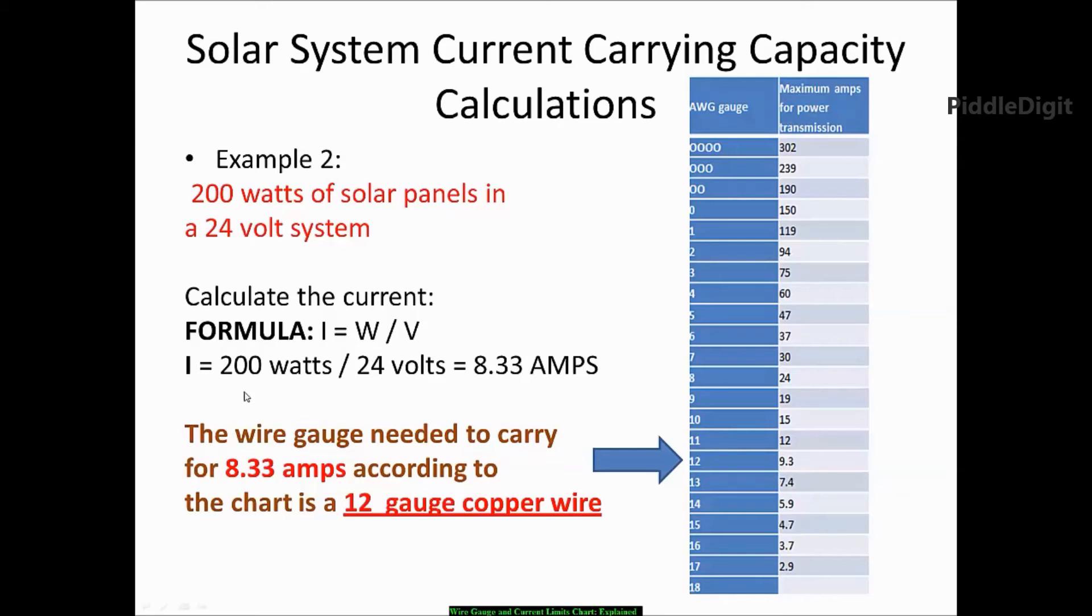So 200 divided by 24 equals 8.33 amps. If we reference the wire gauge and current limit chart, 8.33 amps is not on the chart. I see 7.4 and 9.3. Now, because 8.33 amps is greater than 7.4 amps, we will go up to the next value.